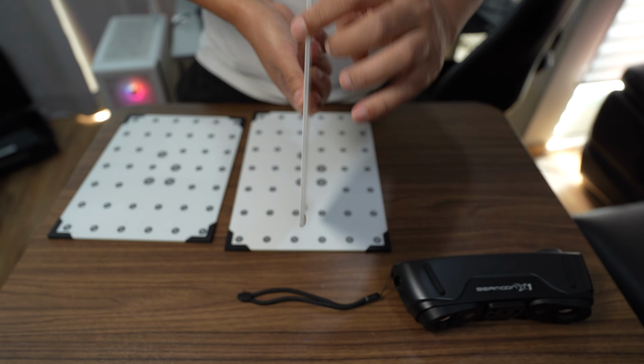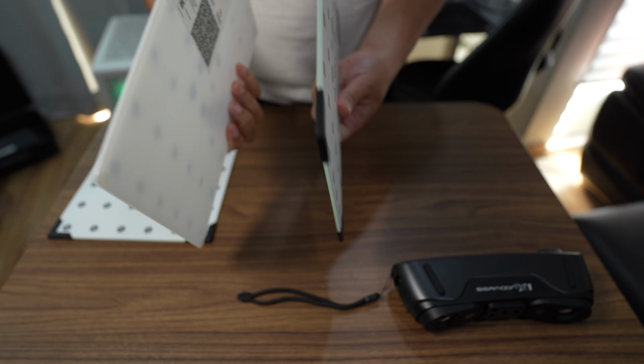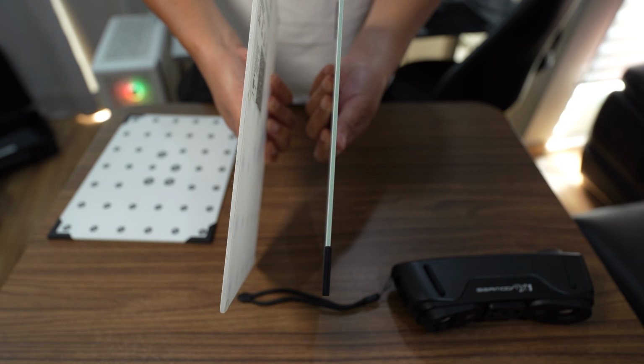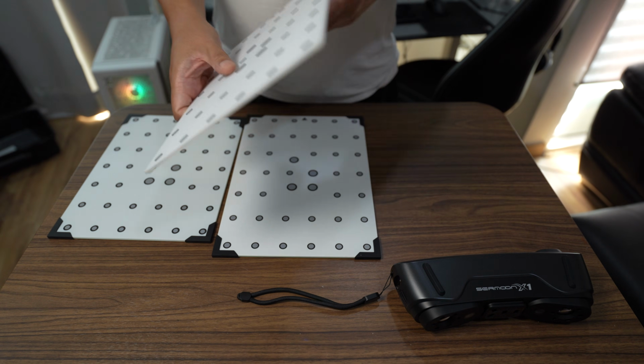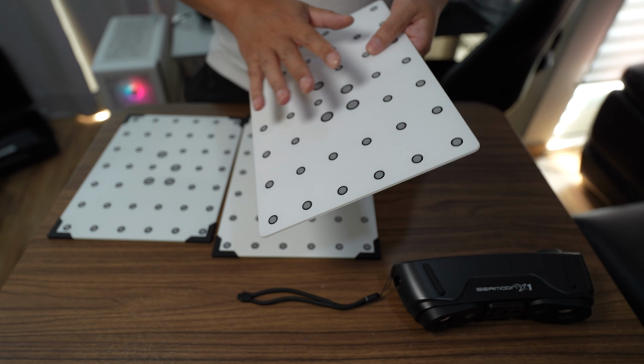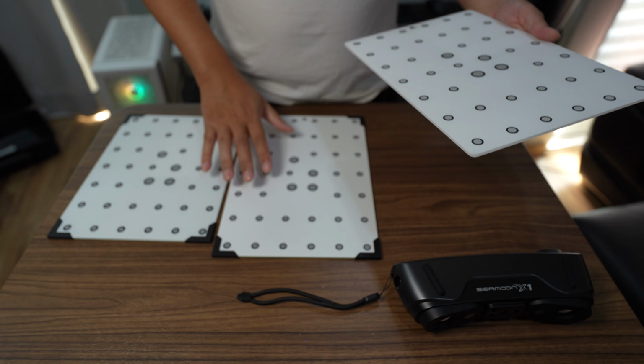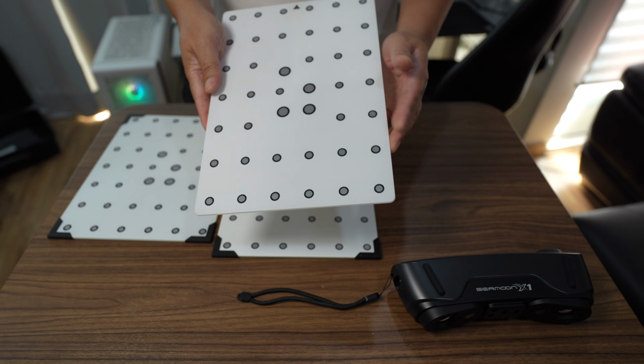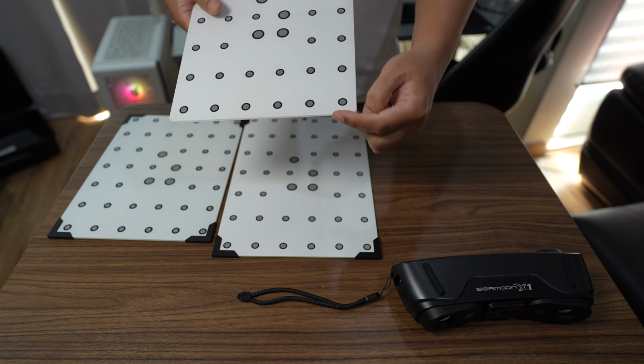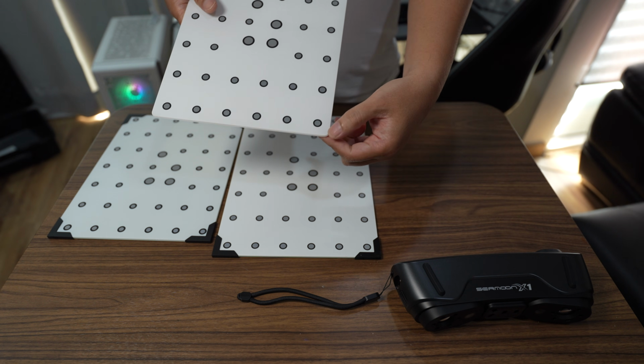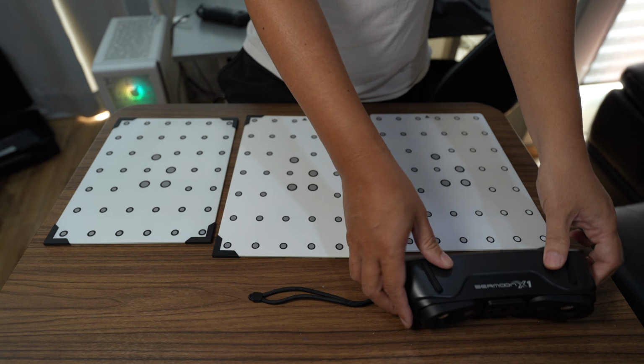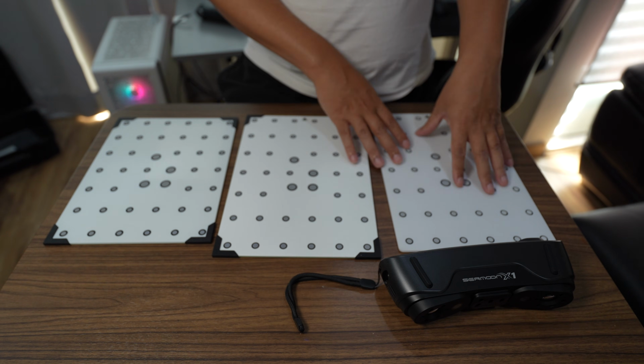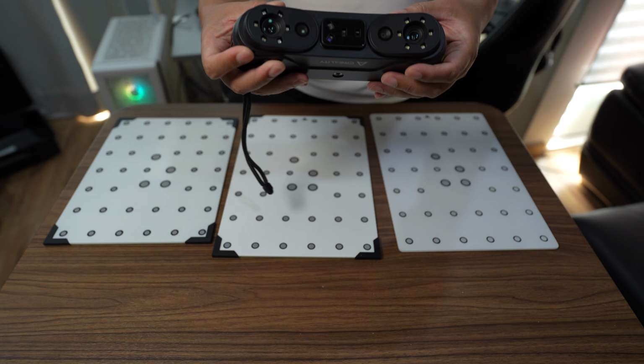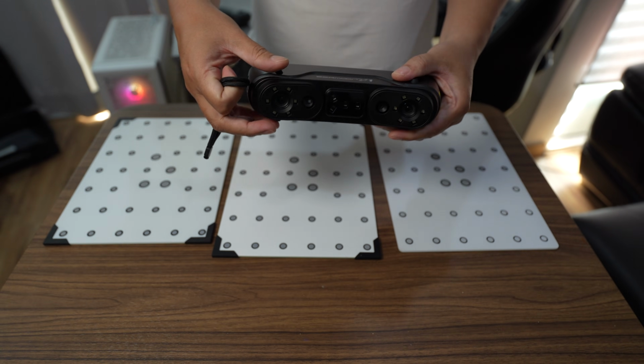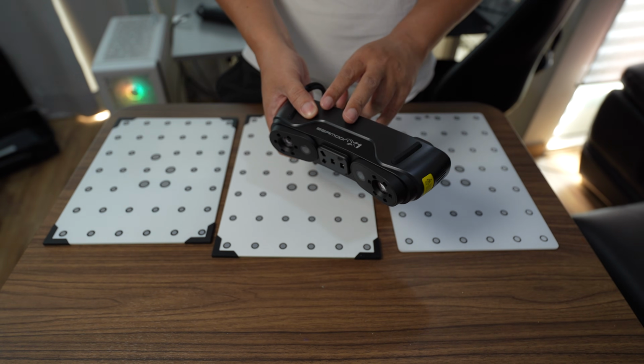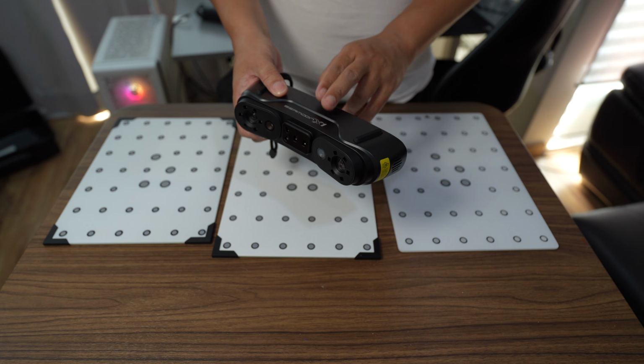And if you look at the color here, it is different from the glass calibration board. Quartz has 6 times less thermal expansion than tempered glass. This is the most stable material. The one that comes with the X1 doesn't have this protective corner. So I test the X1 regularly. Without calibration, it still maintains the accuracy. Even though I used it quite a lot during the past month, I still get 10 microns of accuracy error in the 7-line mode.